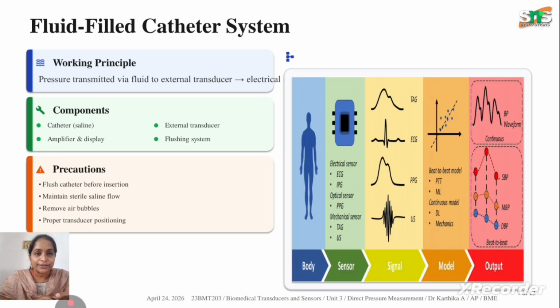See the fluid filled catheter system and output. The working principle is that pressure is transmitted via fluid to an external transducer, which converts it into an electrical signal. See, this involves a catheter, external transducer, amplifier and display, as well as a flushing system. See the output: from the body, the sensor sends the signal. The signal is modeled, and finally we get the output.